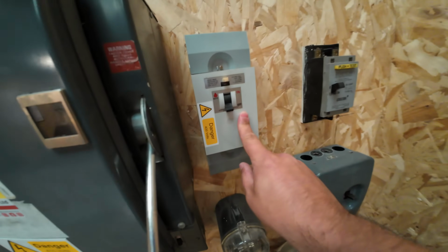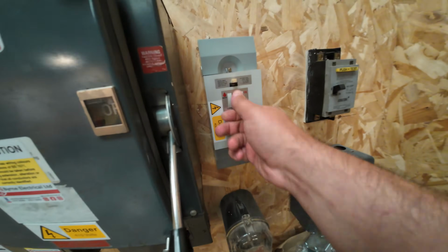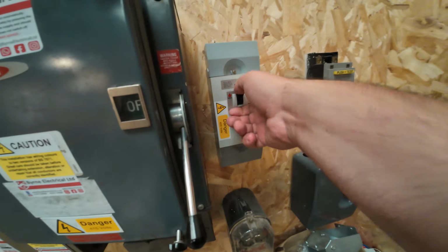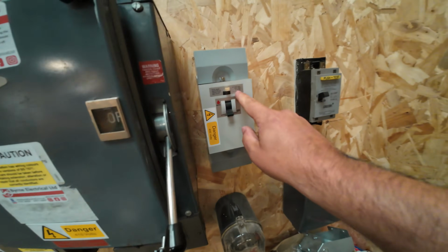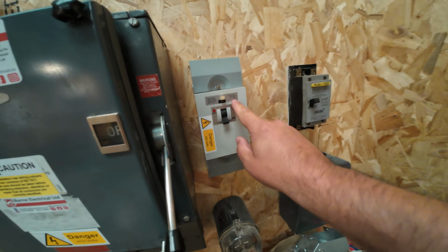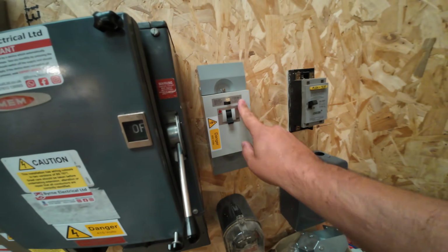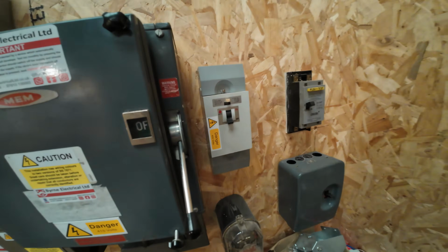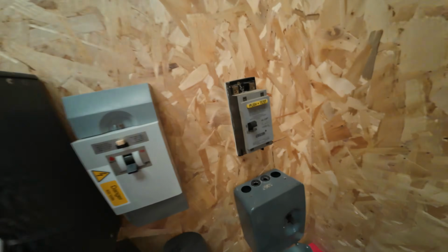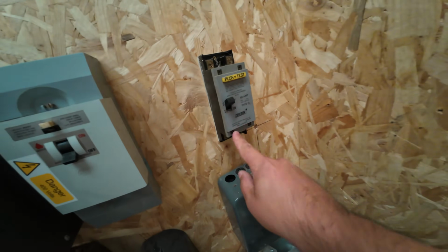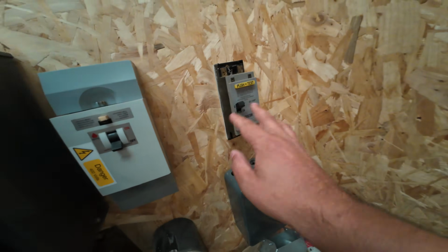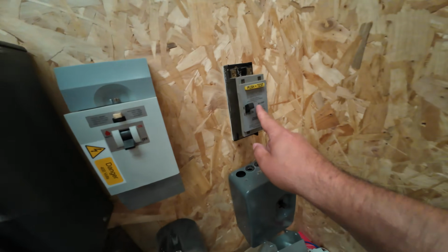And we've got a residual operated circuit breaker here - you can see this is a big old one. This is a 415 volt, 50 hertz, 100 amp, 30 milliamp trip. This is what you would have normally had as a main RCD on an older installation. You've got a 60 amp one too. These are similar to how we would term an RCD, but they behave in a slightly different way.